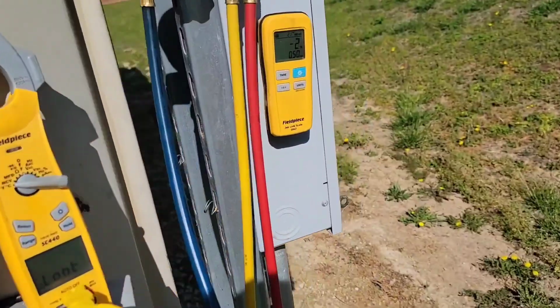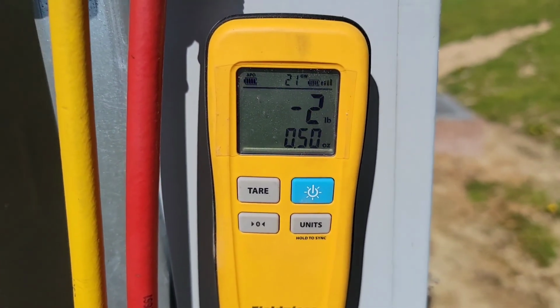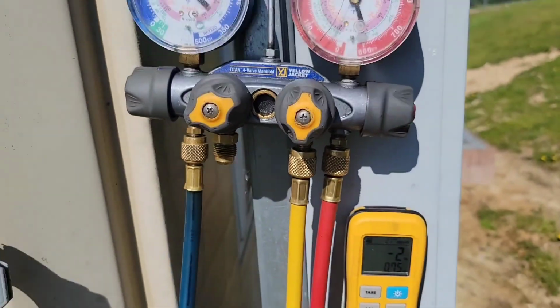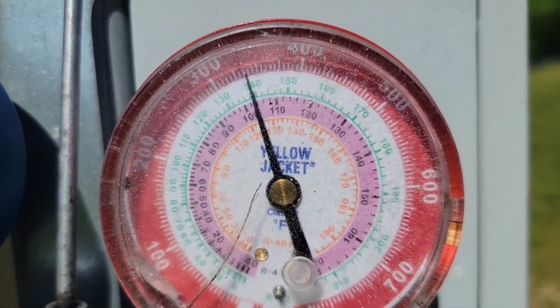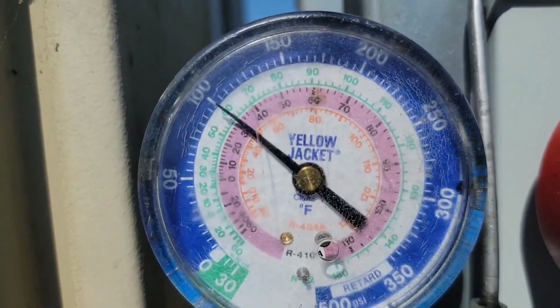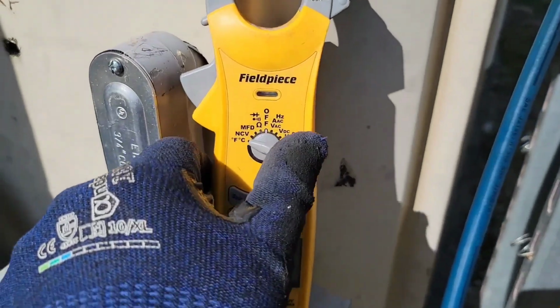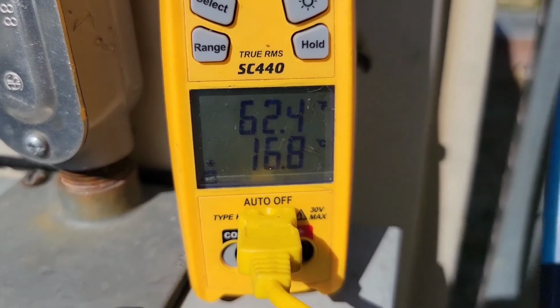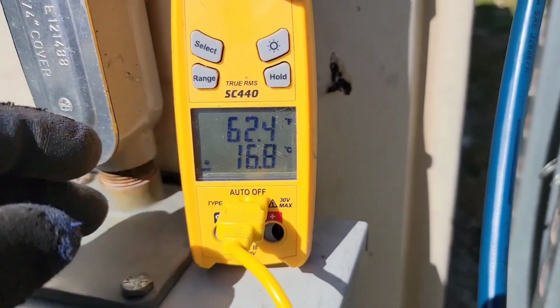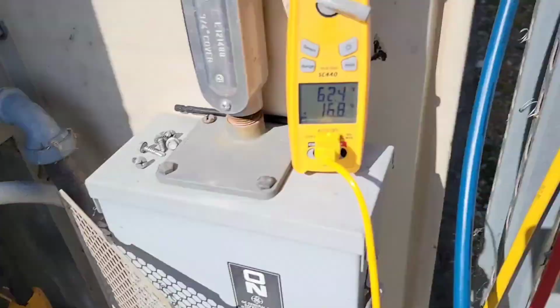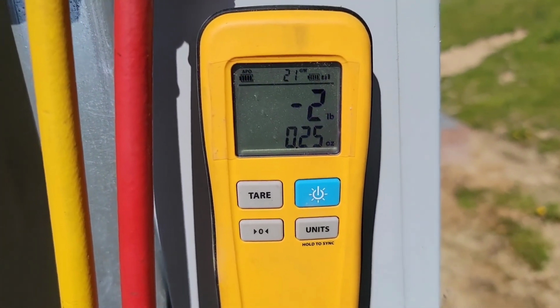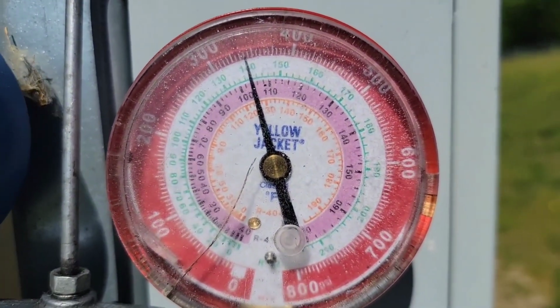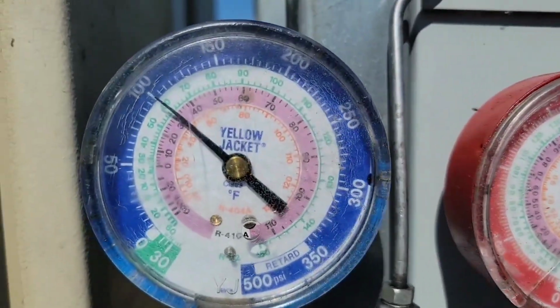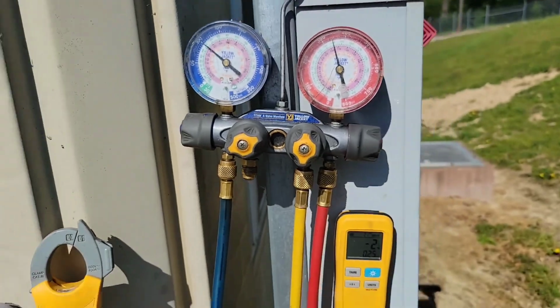Okay, let's see what we got. So we've added 2 pounds of 410A. Head pressure is now 335 and 100 for the vapor pressure. Suction line temperature now is 62, so that's awesome. We've added 2 pounds of 410A. Head pressure is about 335. Suction is 100, so we're getting close to being charged now. Look at that, 61. Oh, low battery.